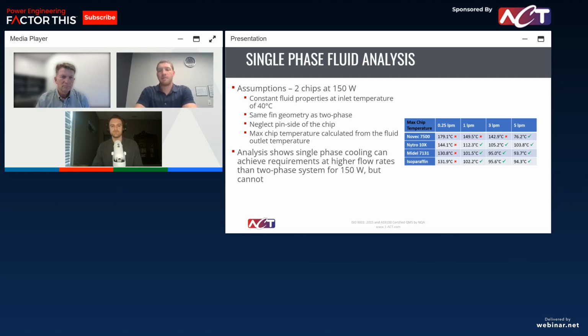Yeah, so I guess evaporator is probably the broader term. Evaporator really comes down to where we're collecting the heat. So wherever your heat generating components are, sometimes we might have an evaporator collecting heat from ambient air from a server rack. But evaporator is really the term we're using where our fluid is coming in there, and then it's boiling, and it's at that saturation.